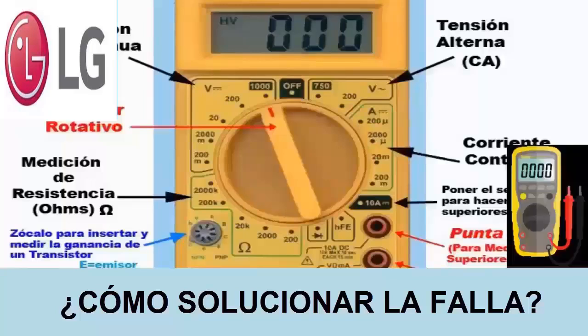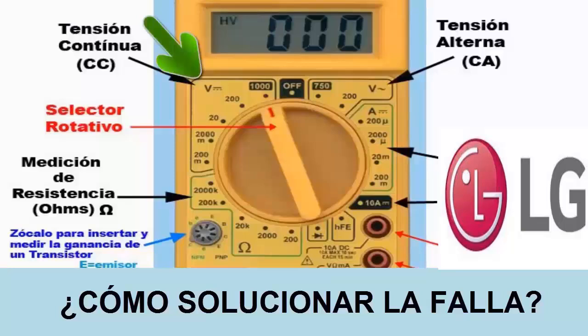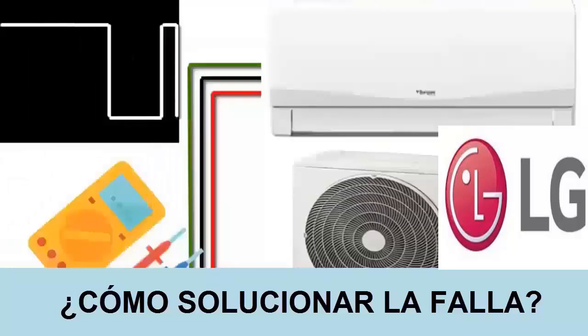5. Measure the signal voltage, which should be measured between the wire connected to the S terminal and the neutral wire, placing the red lead of the multimeter on the signal wire and the black lead on the neutral.